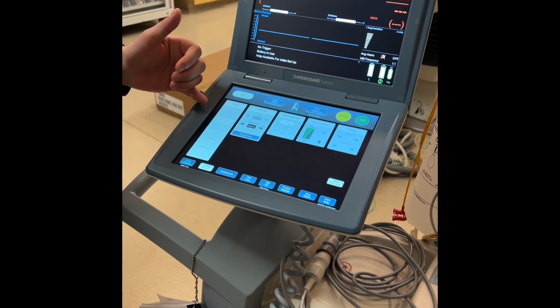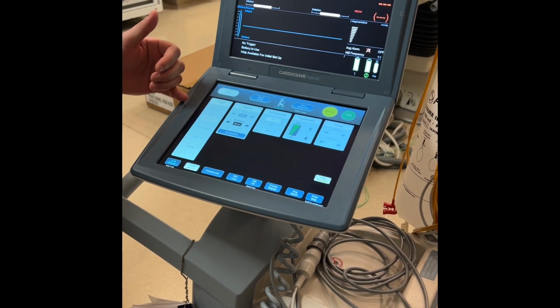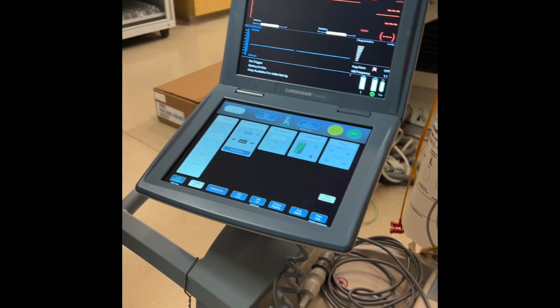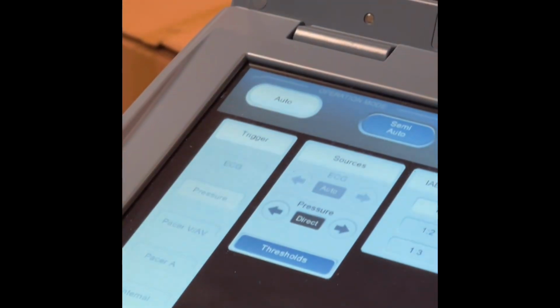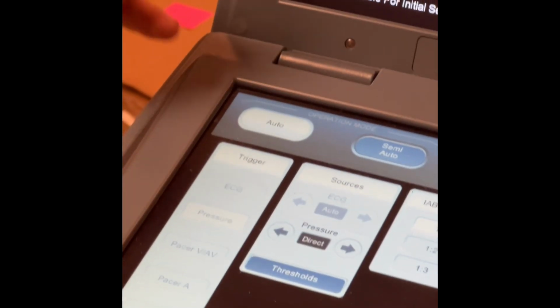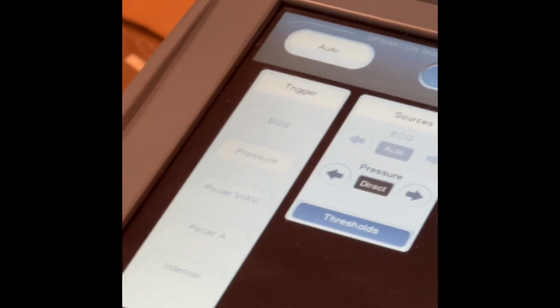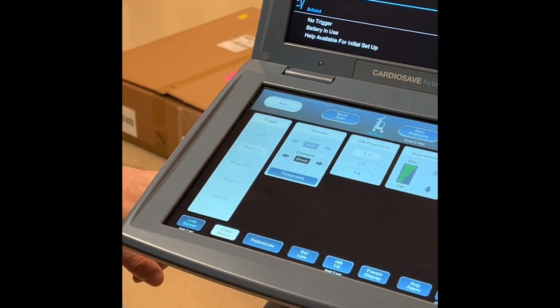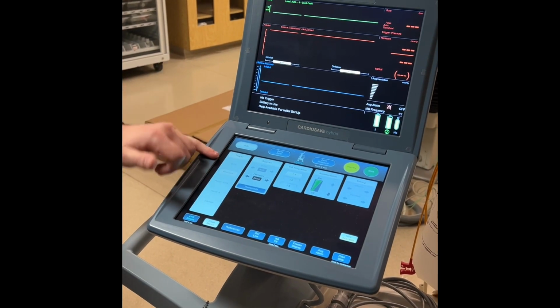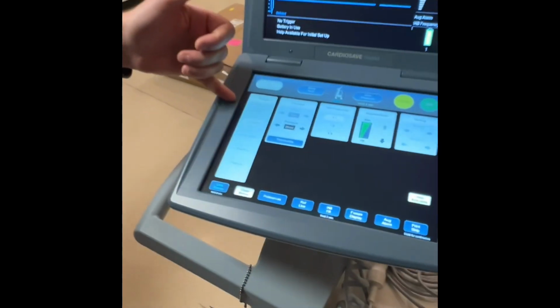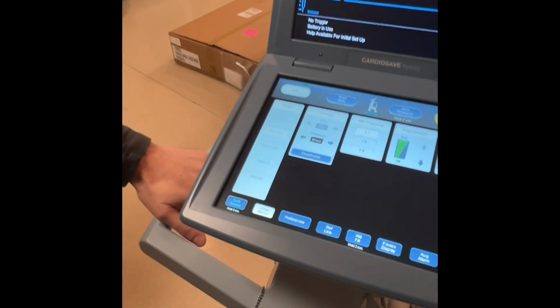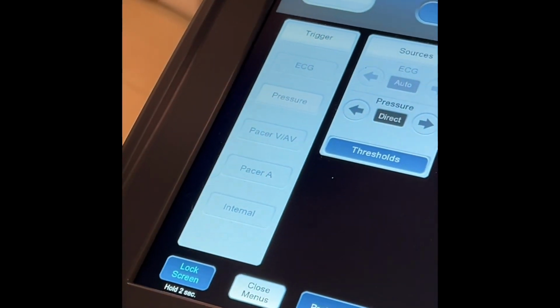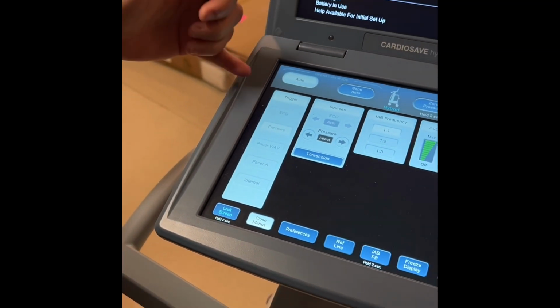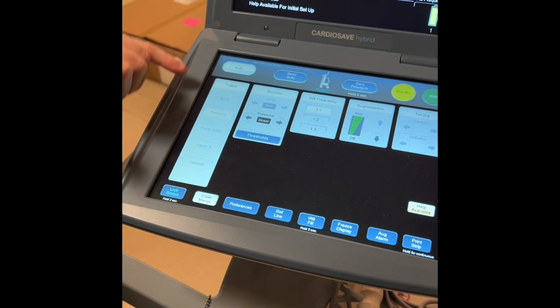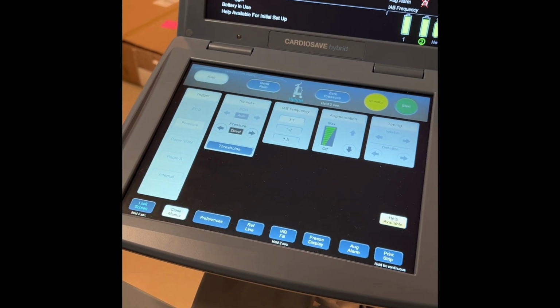So just to touch on triggers for a moment. Earlier I had said that if you can't get the ECG leads on right away, it's not absolutely crucial. And that is because when you're in auto mode, it is going to select the most optimal trigger you have available. So if you have the fiber optic cable plugged in, then it's going to trigger off that fiber optic cable. But if you look at the list here, ECG is at the top of the list, and that is because it is actually the most optimal trigger. So as soon as you can get the ECG leads on, get them on the patient, and then with it being in auto, it's going to automatically switch itself to the ECG trigger.